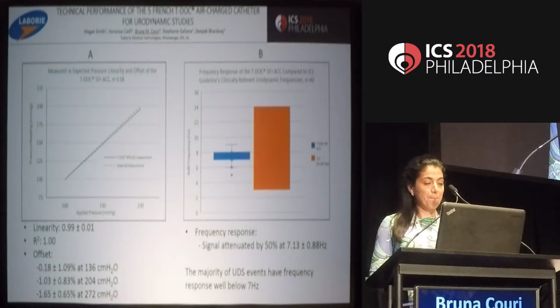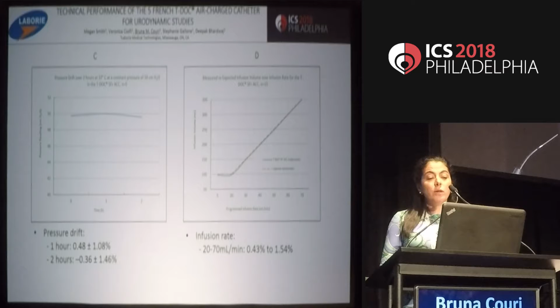Pressure drift tests were done during 2 hours. And at the first hour, we observed a reduction in pressure of 0.48% with a standard deviation of 1.08%. At the second hour, we observed a mean of negative 0.36% with a standard deviation of 1.46%. The infusion rate mean between 20 and 70 milliliters per minute was 0.43% and varied to 1.54%.